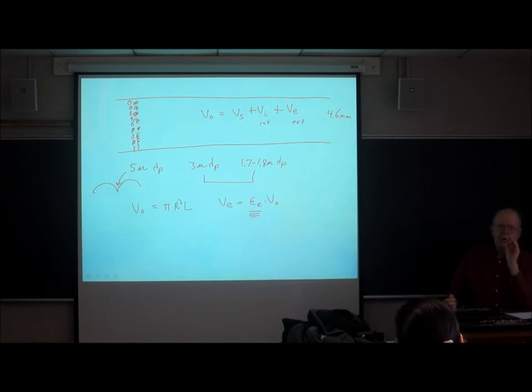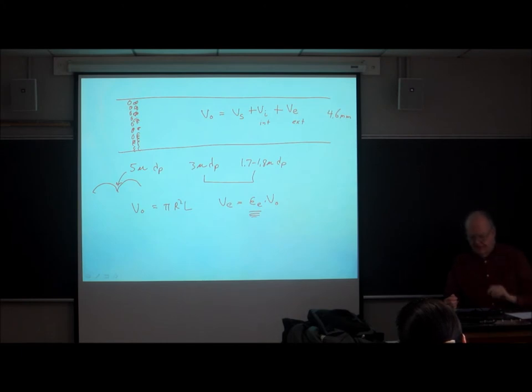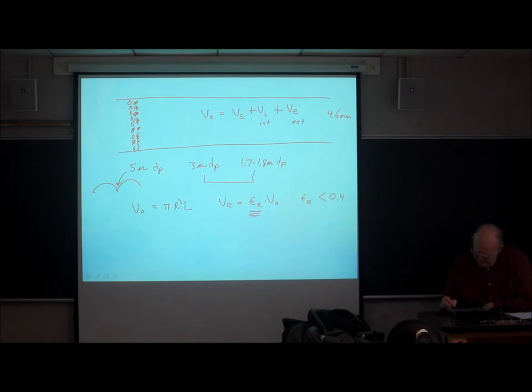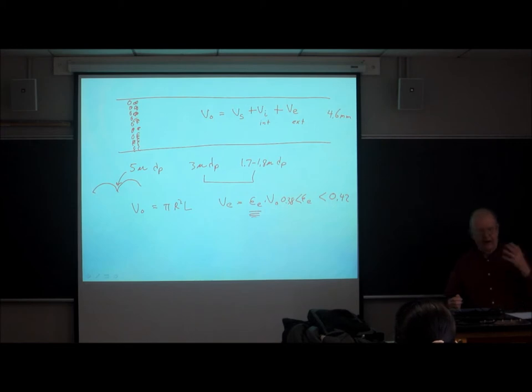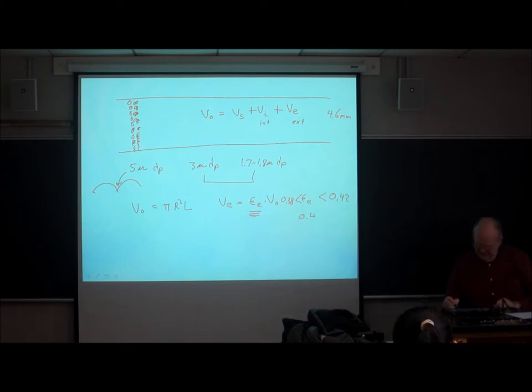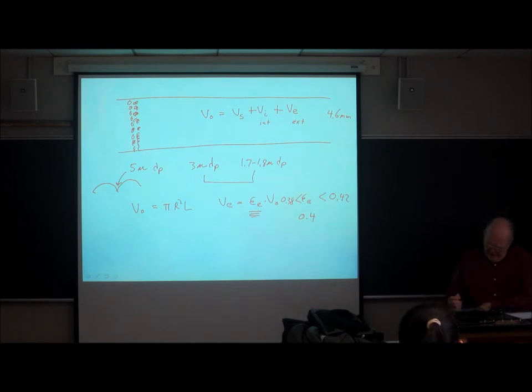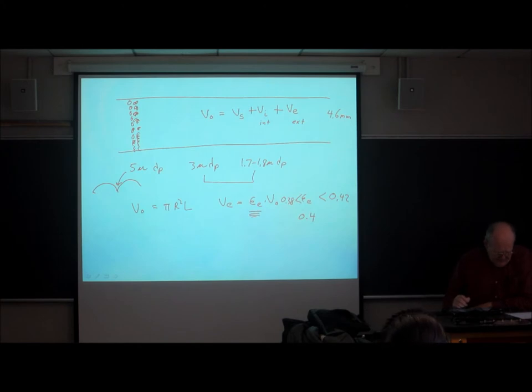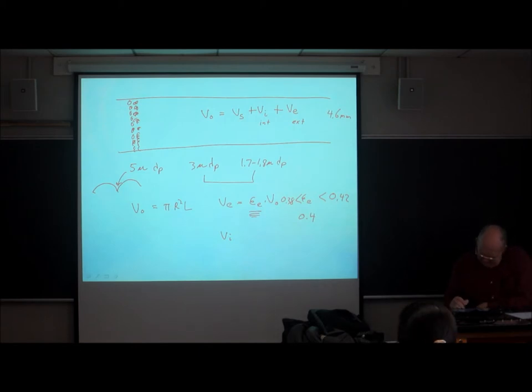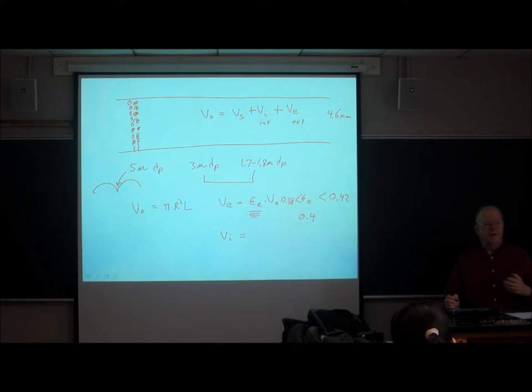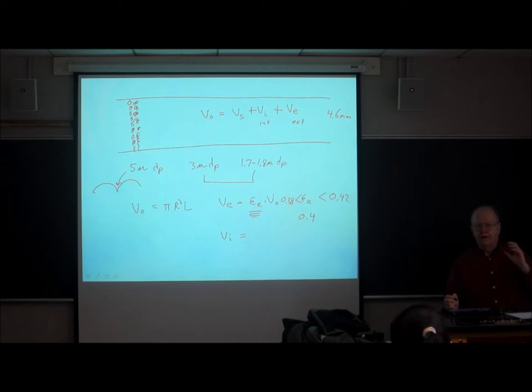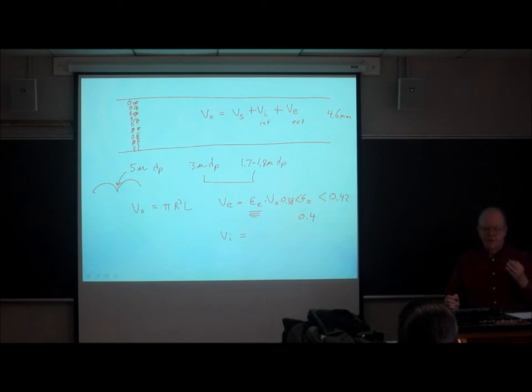The external volume equals the external porosity times the total volume of the unpacked tube. The external porosity represents the spaces between the particles — the fluid in the cusps between touching particles. In a well-packed HPLC column, this number is typically between 0.38 and 0.42; 0.4 is a good working value.